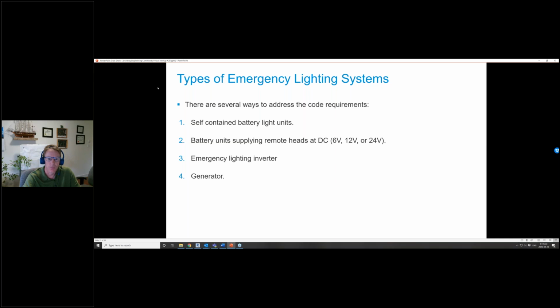Okay, so now into the types of emergency lighting systems. You can meet these code requirements in a few different ways. One is with self-contained battery units. Second is battery units that supply remote heads operating at a DC voltage, typically 12 volts for us, but it can also be 6 volts or 24. Another one is an emergency lighting inverter. Another is a generator. So I'll get into all these a little bit.